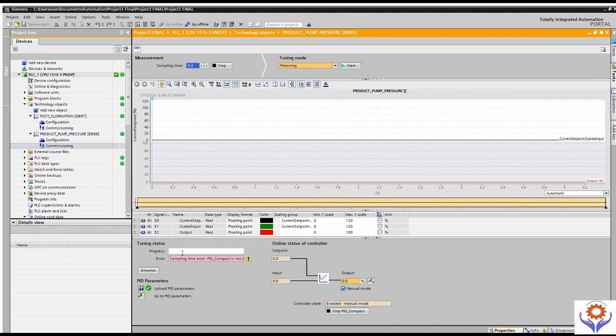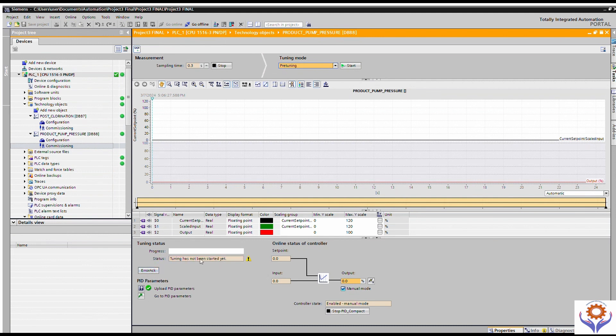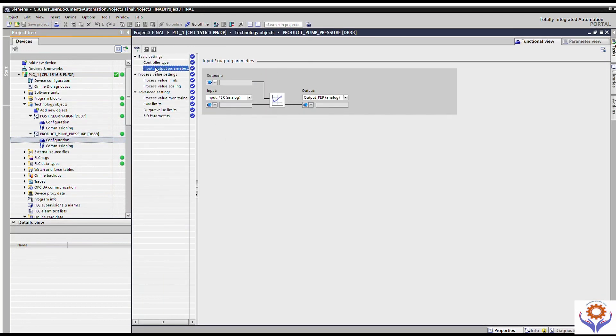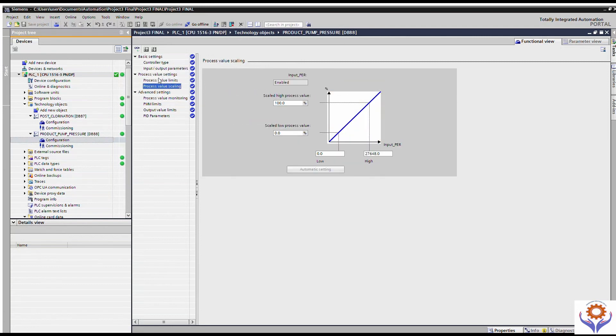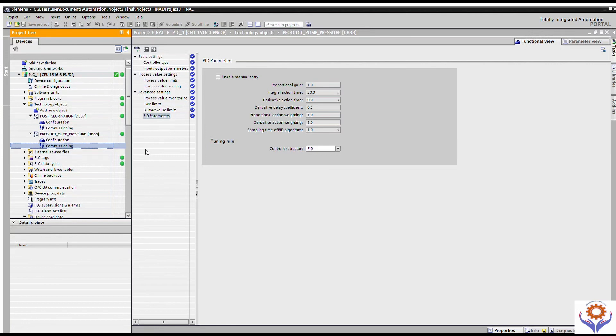For the post-chlorination PID, it's already connected and you can see some values in the input. The output is not given because I don't want to disturb the running system. This is how we do tuning — if you go to Tuning Mode, click Pre-Tuning Start, and it will tune automatically. As per the tuning, you can see the performance of the PID values. This is the overview of the PID controller in the Siemens S7 series — you can use S7-1200 or S7-1500 controllers and make the tuning as per your configuration.